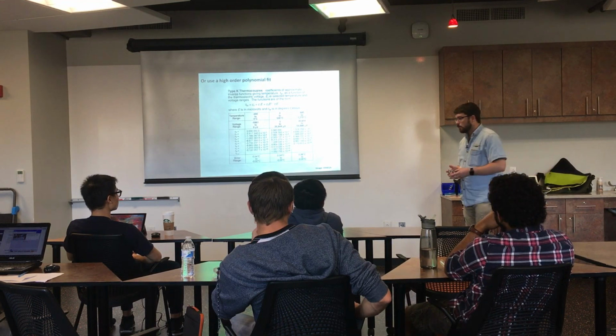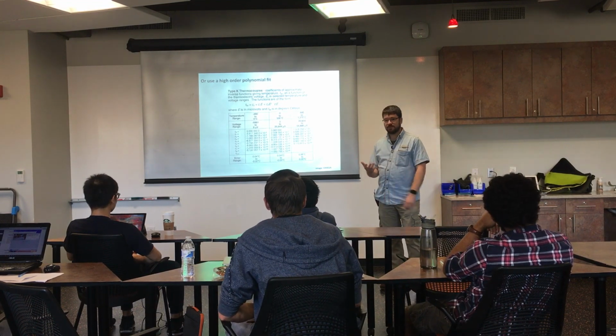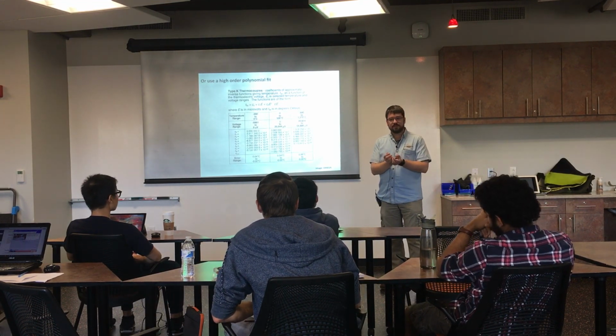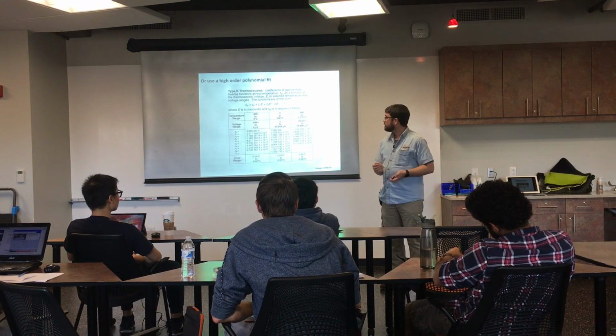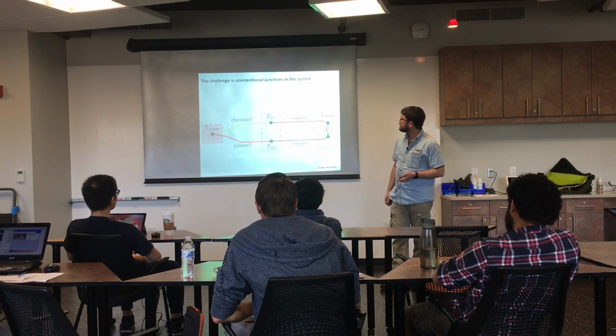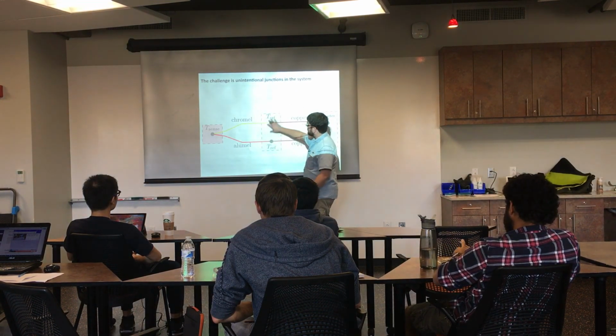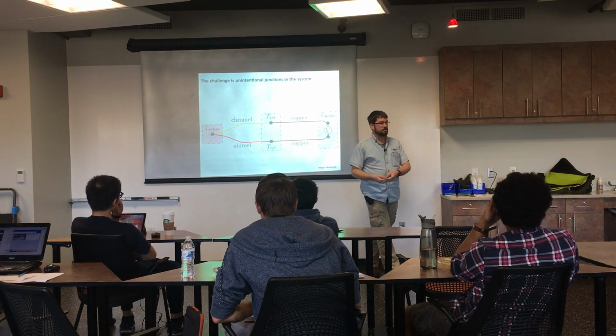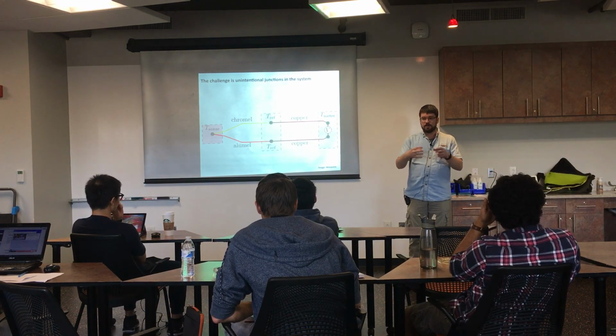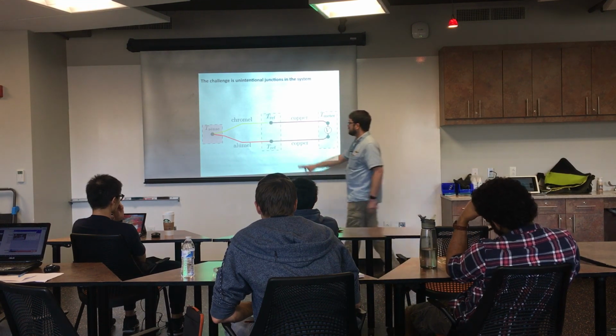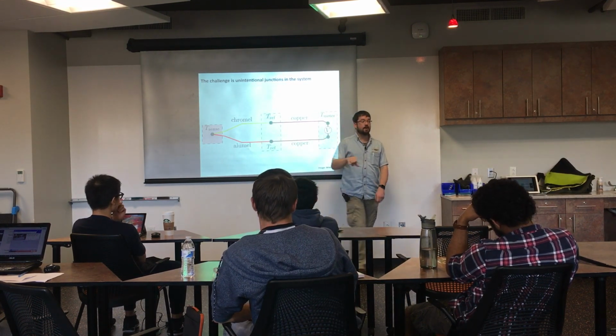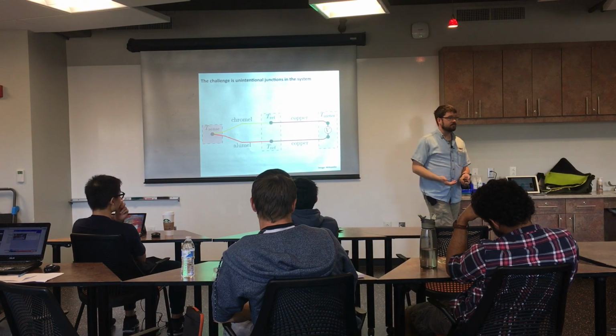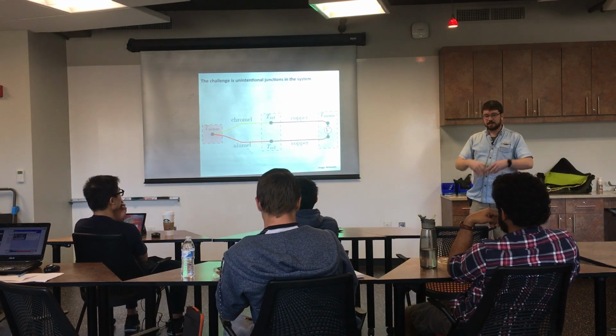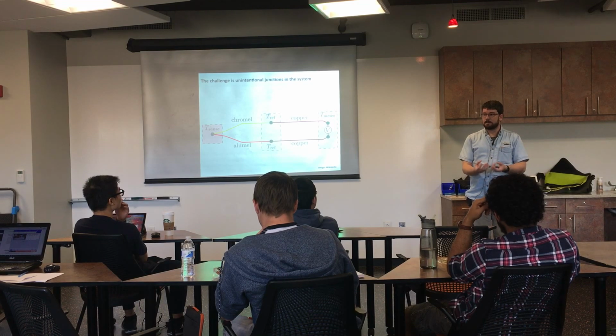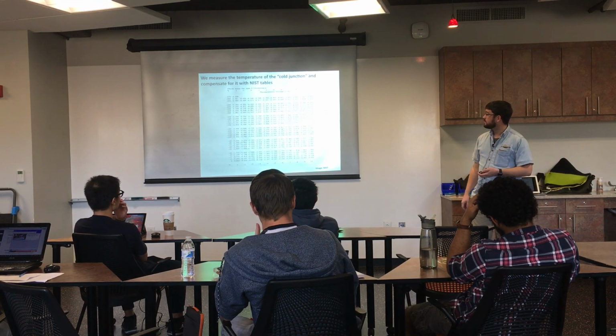When you're looking for a thermocouple signal processing unit, a lot of times you'll see they have an isothermal block, meaning where you attach the thermocouple to your National Instruments card or whatever, there's a very thermally conductive, massive material so that both junctions sit at the same temperature, typically room temperature, so your cold junction correction works well. If you take the circuit board apart, you'll see big areas of copper and huge metal studs meant to keep everything at the same temperature.